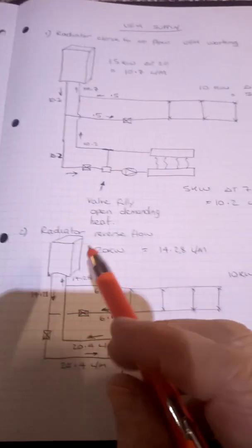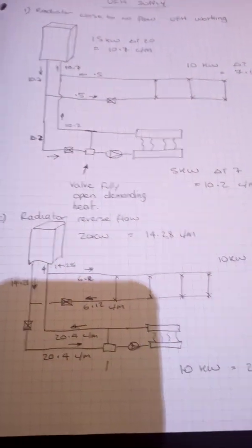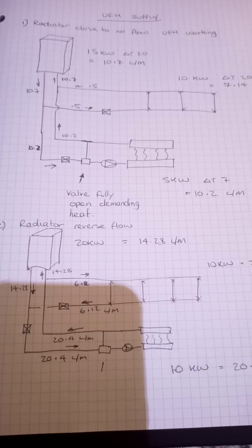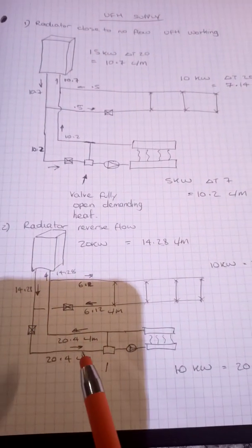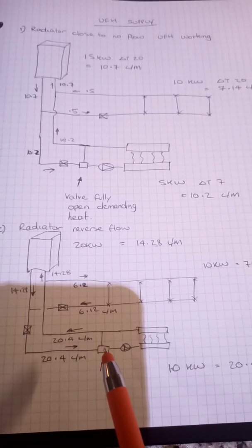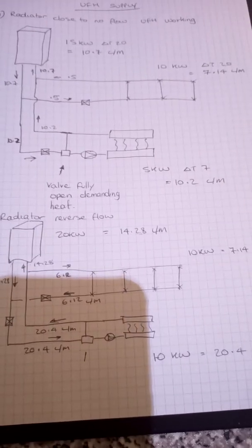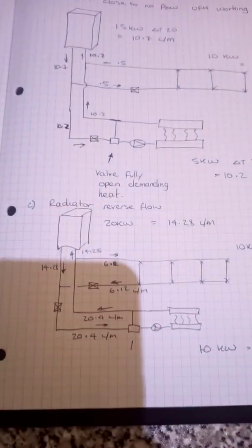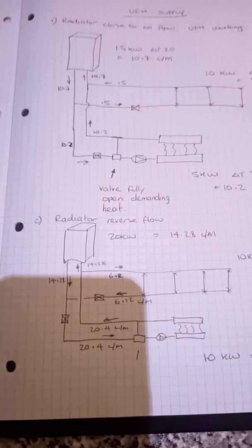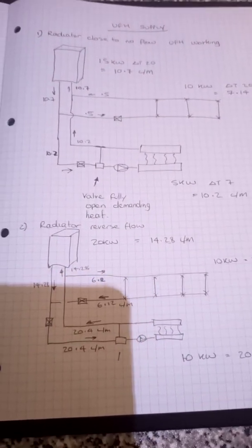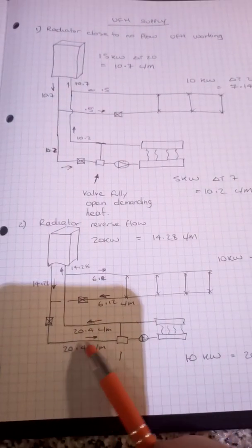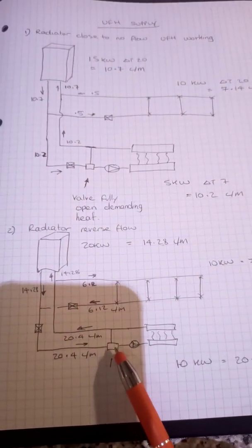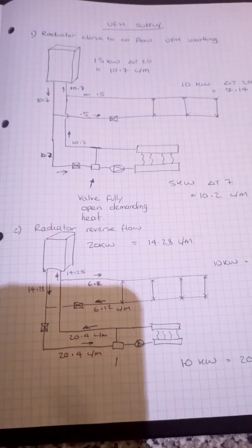And they still repeat this habit on modern boilers, setting the dial to number three, which of course causes low temperature output from the boiler, especially on combination boilers, this one. And the underfloor heating manifolds, typically they've turned the temperature up to 50 or so on there because the underfloor heating isn't warming up quick enough because they've got on-off controls and not using a setback. So we end up with a scenario where the boiler's not giving us enough heat to cause the valve to close off, and we've got full flow through the underfloor.